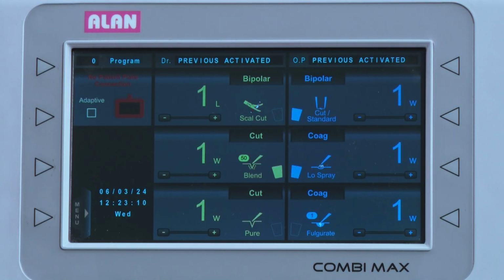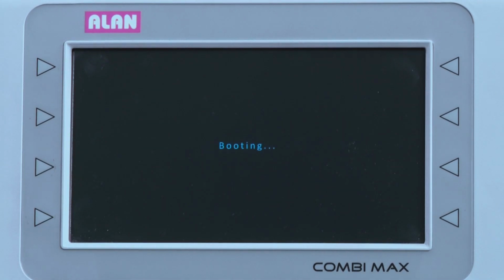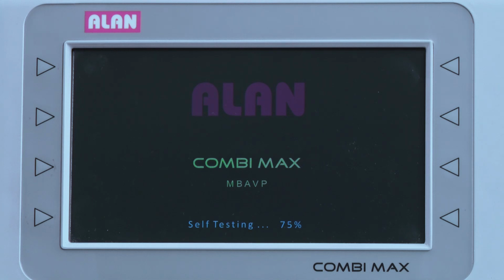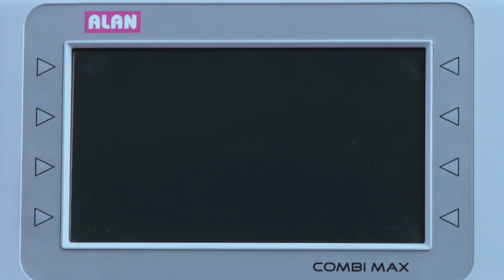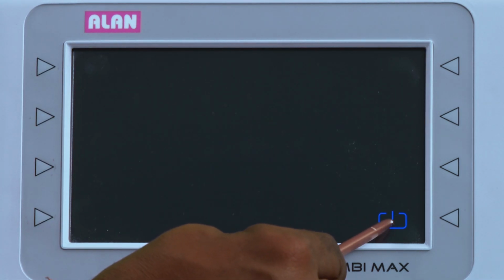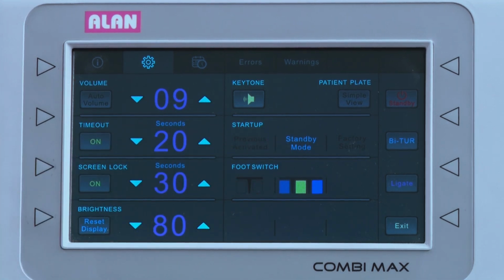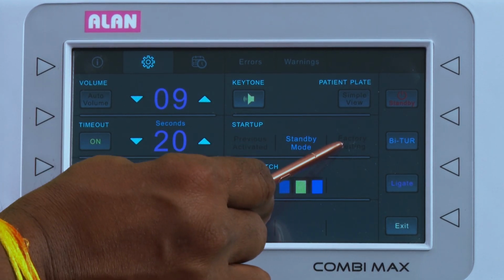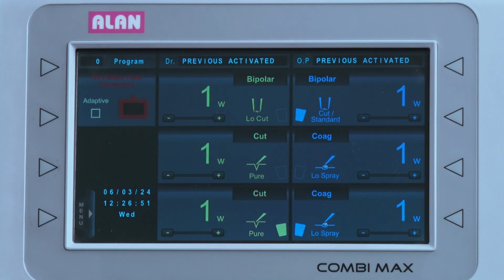In the second scenario, let's see what happens when we select standby mode in startup settings. After the successful completion of self-test, the unit has gone into standby mode. To bring it to the activation, press here. In third situation, let's see what happens when the startup is kept at factory settings. If factory setting option is selected, during power up, the unit will restore all the settings as per factory default settings. All the power levels will be 1 watt.